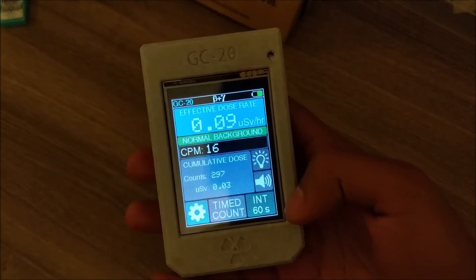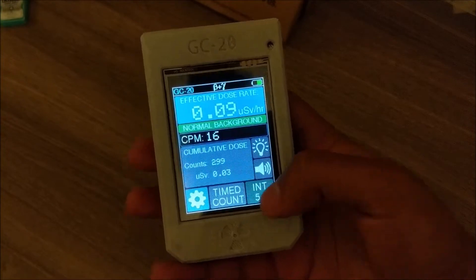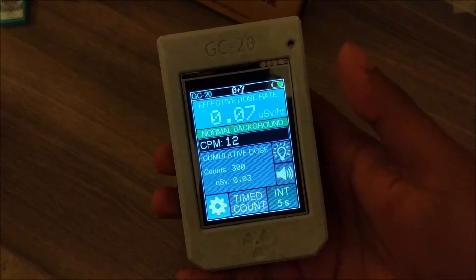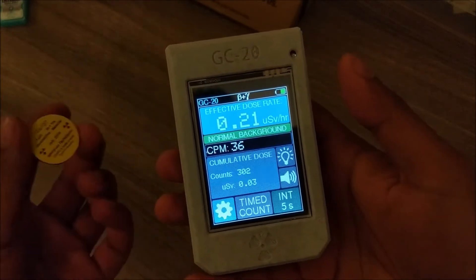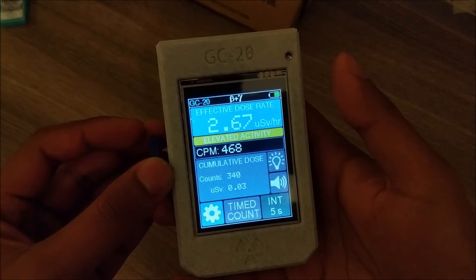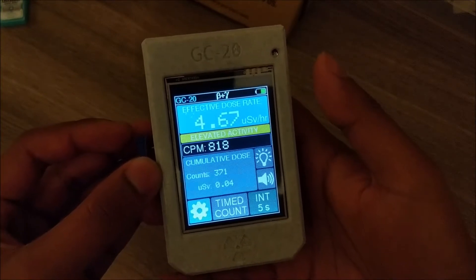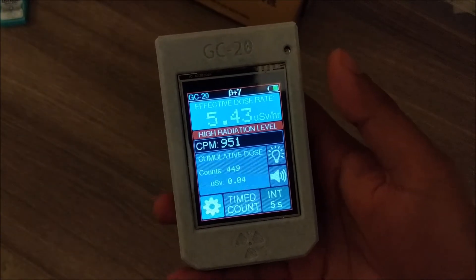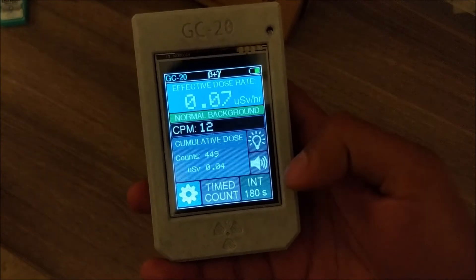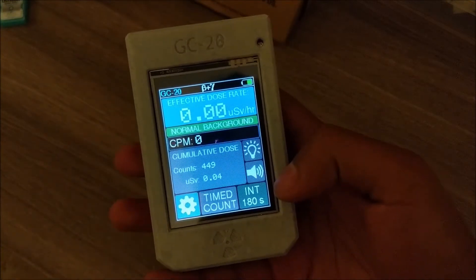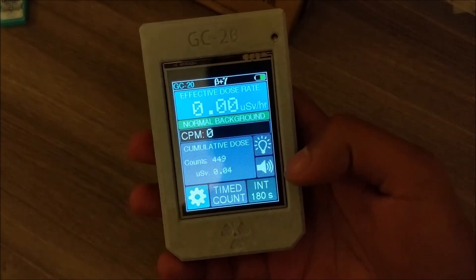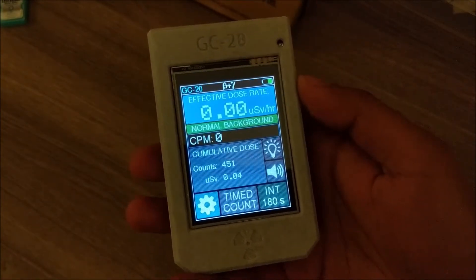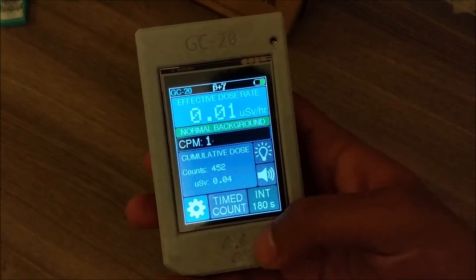It says '60 seconds,' which means the integration time is currently 60 seconds. You can change it to 5 seconds, which makes it more responsive but at the expense of accuracy — you'll see it climbs really quickly and then drops off quickly. You can also change it to 180 seconds, or three minutes, which is useful for measuring low levels like natural background because it doesn't fluctuate as much.